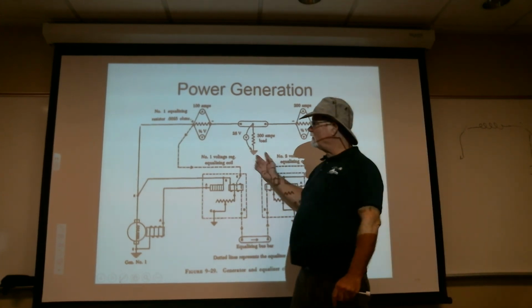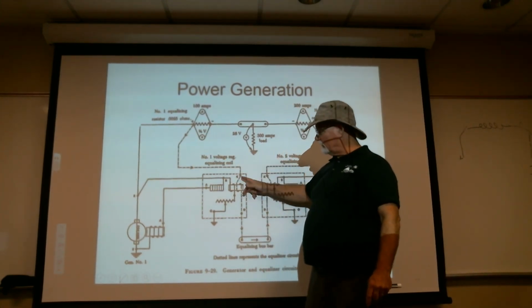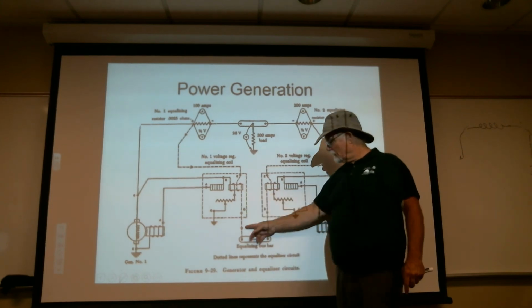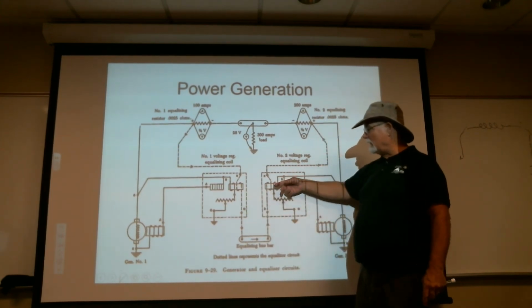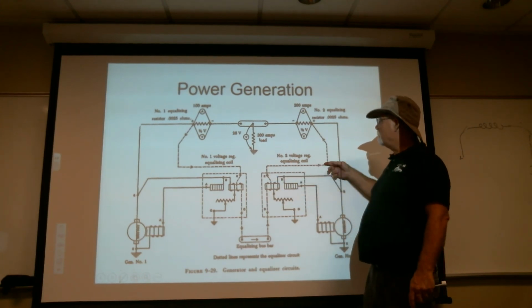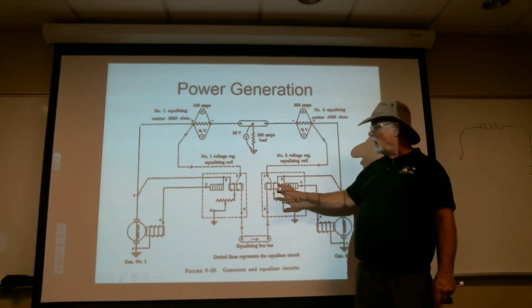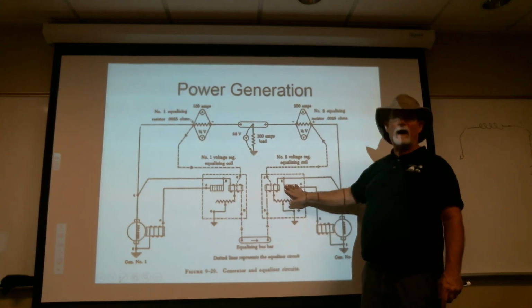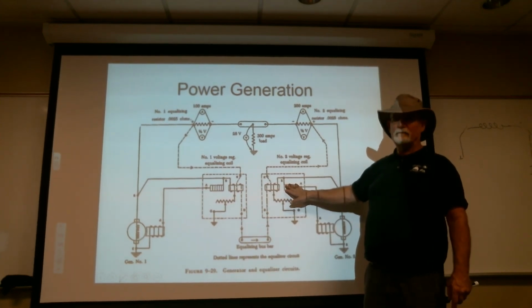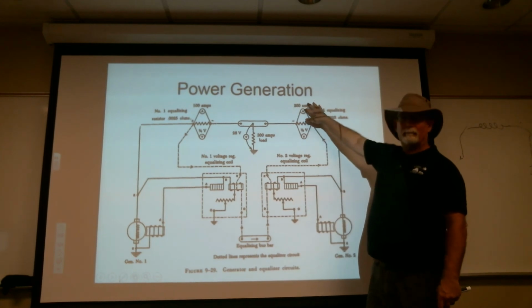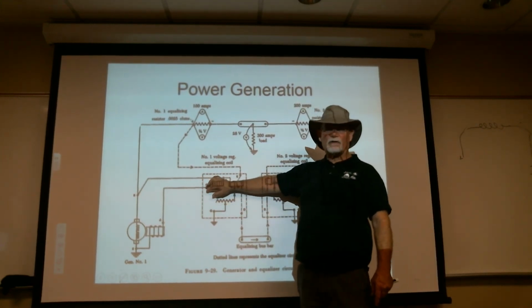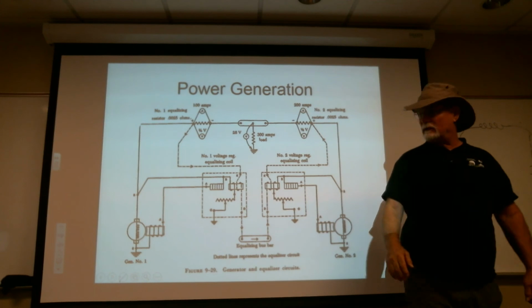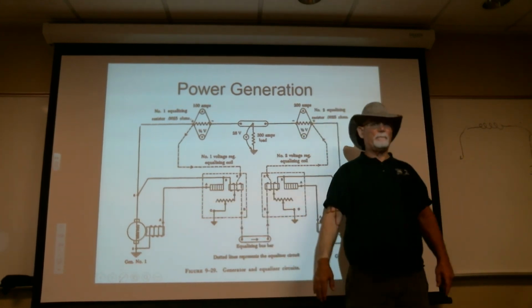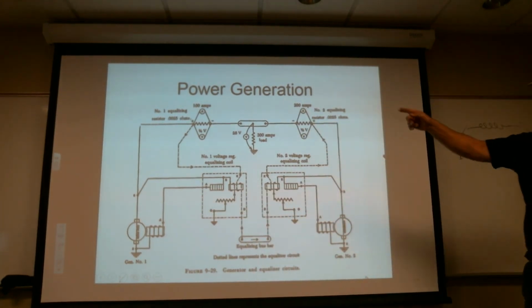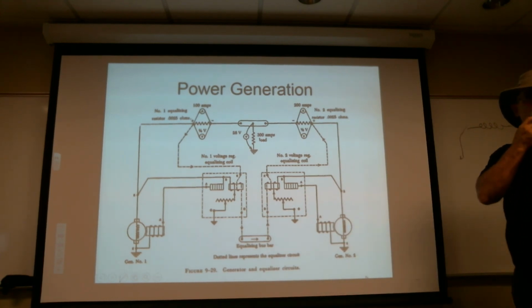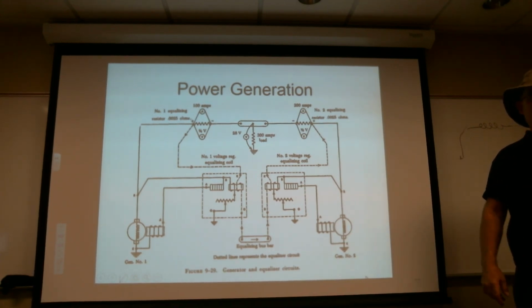That's enough to cause some current to flow through the second equalizing coil, across down to here, through that equalizing coil in the opposite direction, and back this way. That's going to cause, in one case, this carbon pile to back off a little bit, lowering the output and the amperage. And in the other case, it's going to cause the carbon pile to compress, bringing the power output of this unit up some. So it's going to try and get them both to come back to 150. Guys, with me on that?